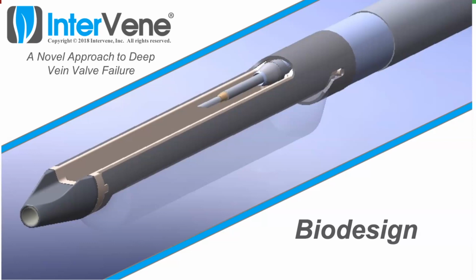There are some benefits in terms of time and cost, et cetera, with being a 510K. And there are some benefits with the de novo because you get to really decide your own labeling and your own claims about your product, what it does. You don't have to be surreptitious in how you describe things in order to fit into a category, because you're making a new category.